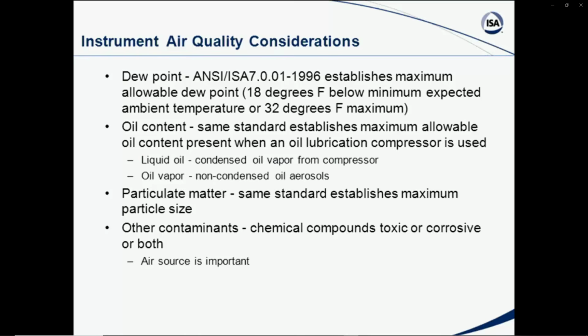So this one establishes a dew point requirement that says it should be 18 degrees F below the normal minimum expected ambient temperature, or 32 degrees F as a maximum.